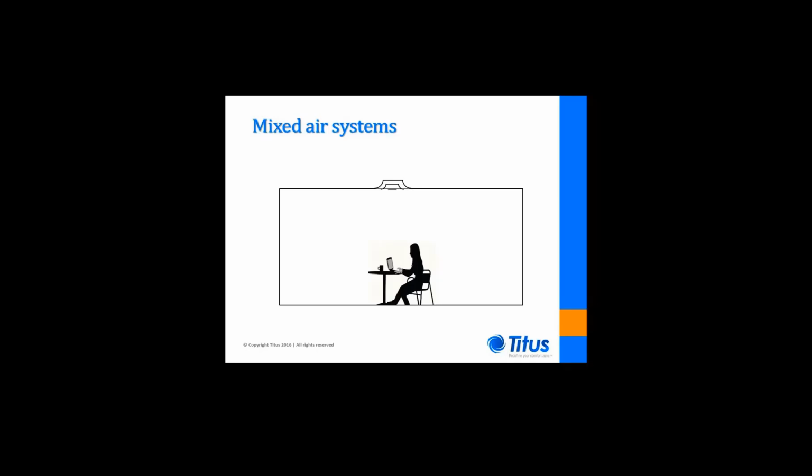These diffusers usually discharge the air horizontally across the ceiling, attempting to make use of a capillary effect of the ceiling surface, which is referred to as the Coanda effect. An adequate discharge velocity is maintained to induce room air and mix it with the cold conditioned air such that the velocity and the temperature differentials are dissipated before the supply air stream enters the occupied levels of the space.